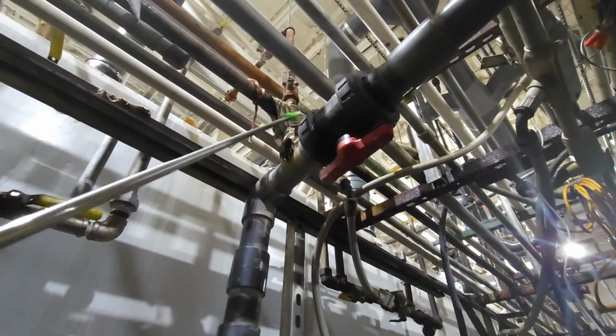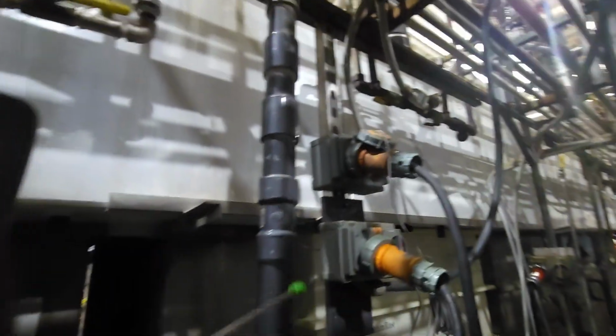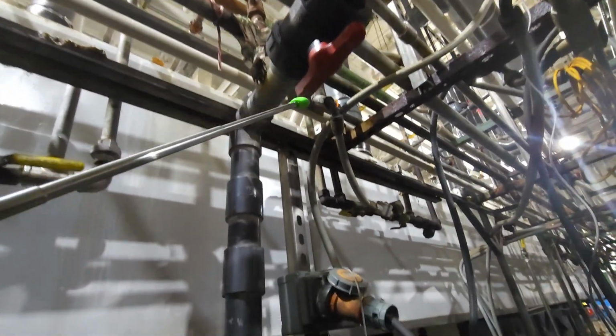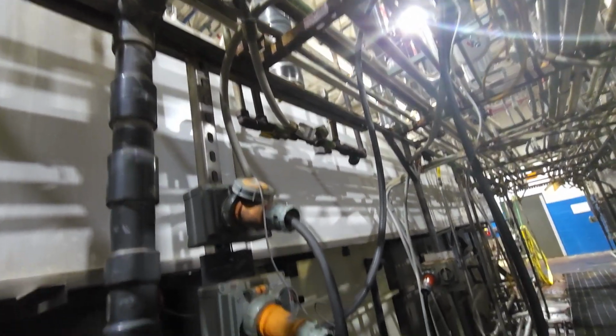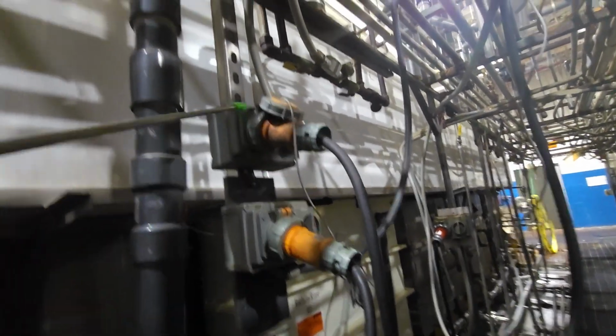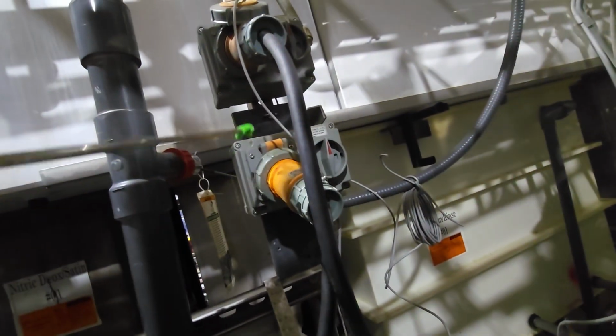And always shut off your valve before doing any repairs. Shut off your power and your valve before doing any repairs. I've had people kill the valve, forget to shut off the power, or shut off the wrong one. Take that second, follow your lineup to see where it goes. I've had people not kill the right one, have this ball check off, and that thing kick on, and yeah, it's a waterfall in this place.